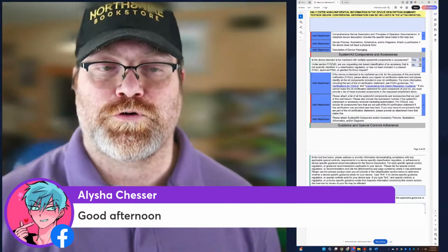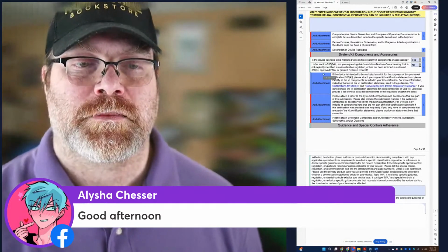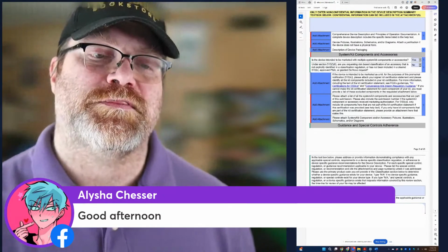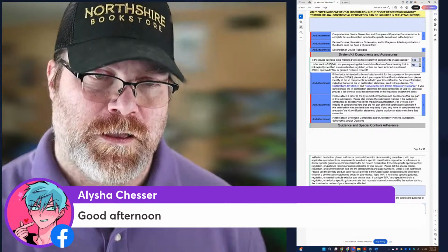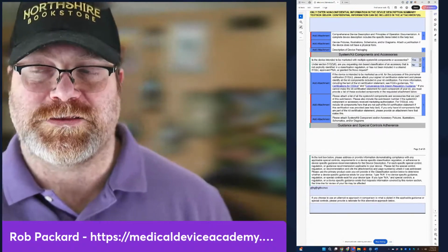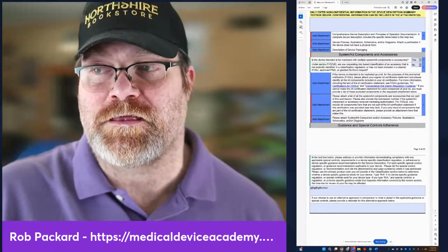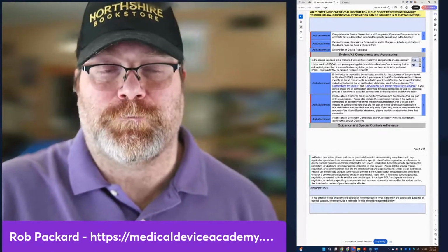So I don't have to put that in the submission anymore. I don't have to put it in the device description anymore. Instead, I put it right in the eSTAR in the place where they designate that I have to put it. And I can't complete the eSTAR until I've done that. So it would be redundant to put it in both places.